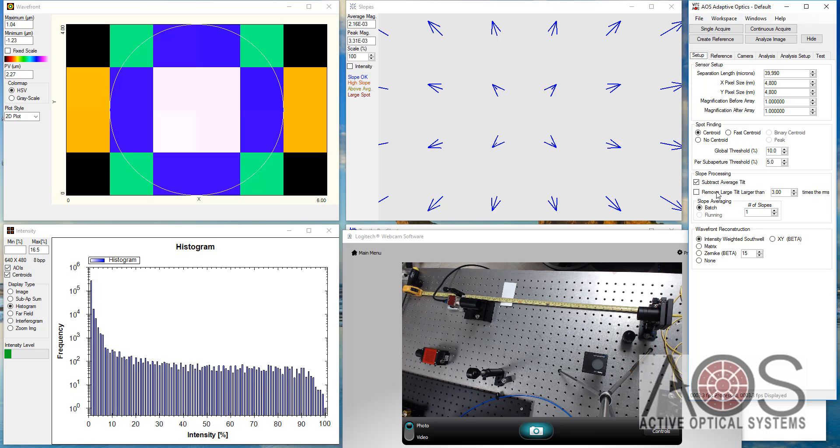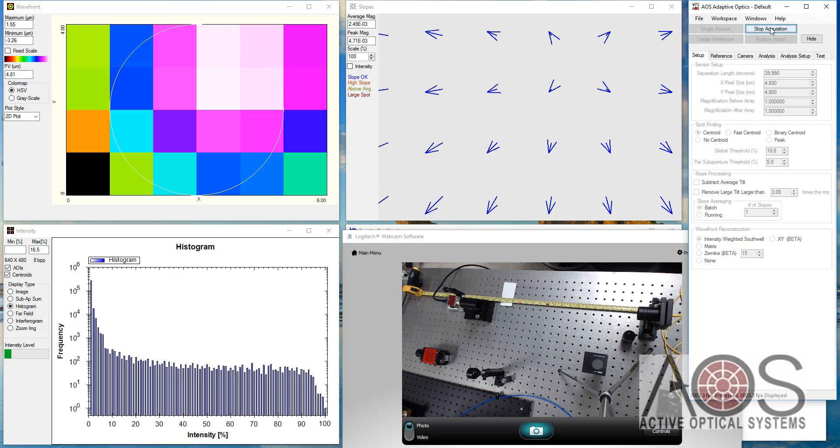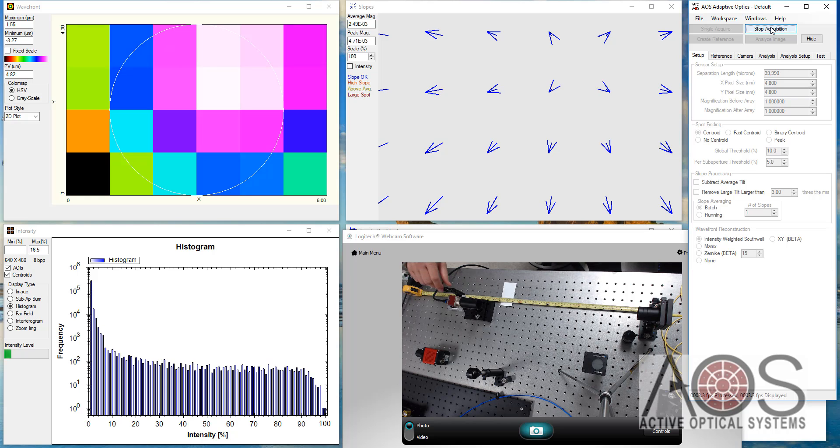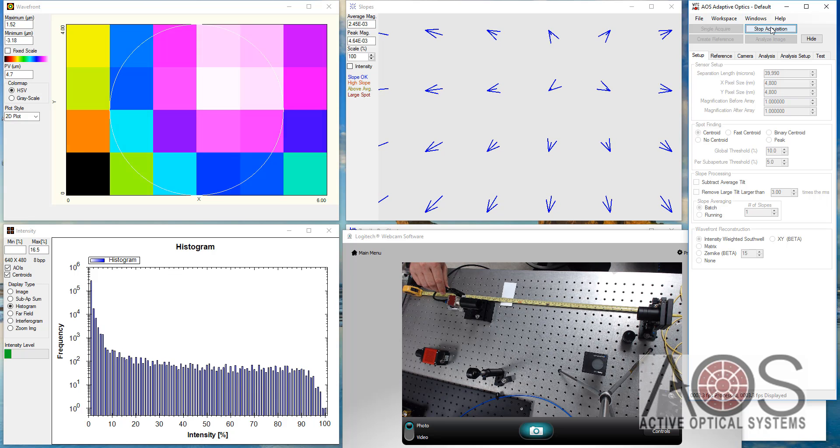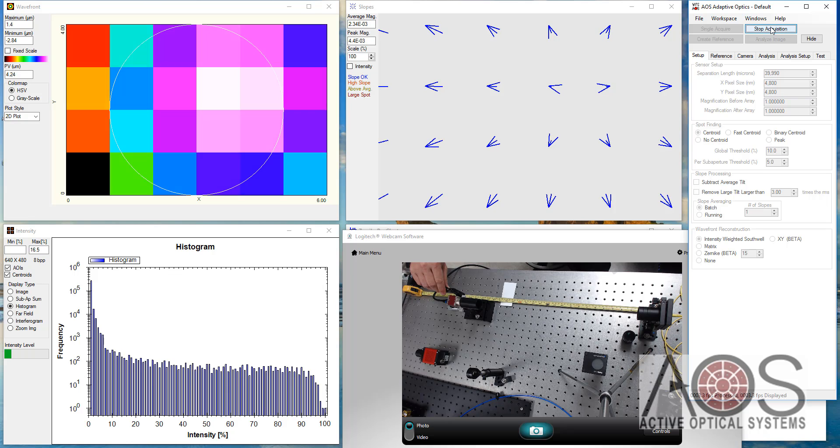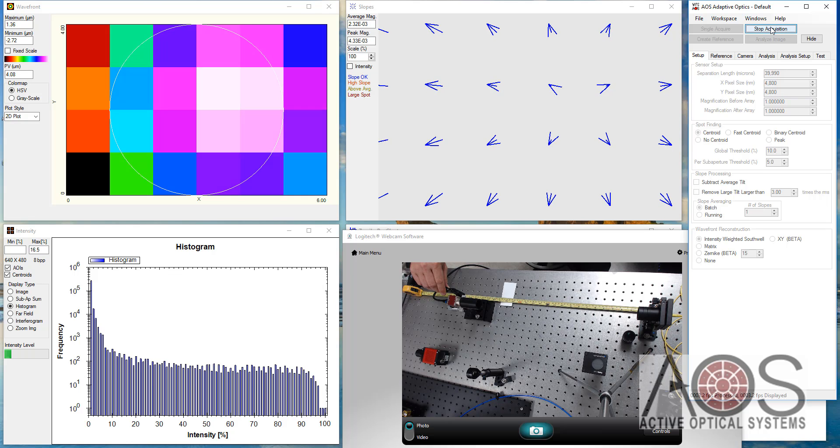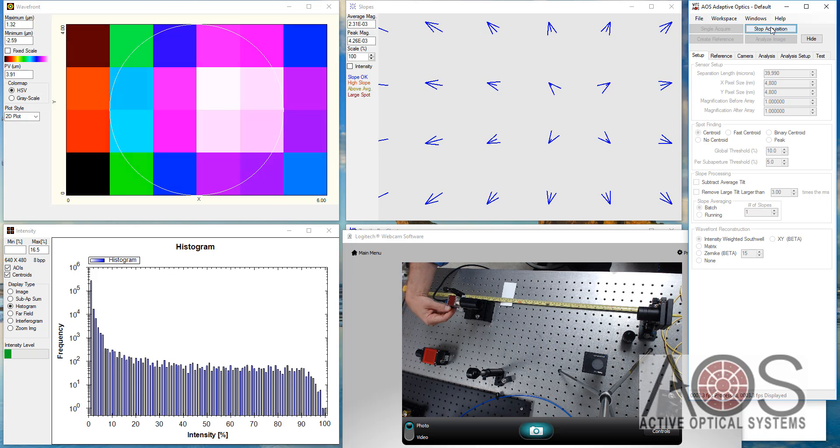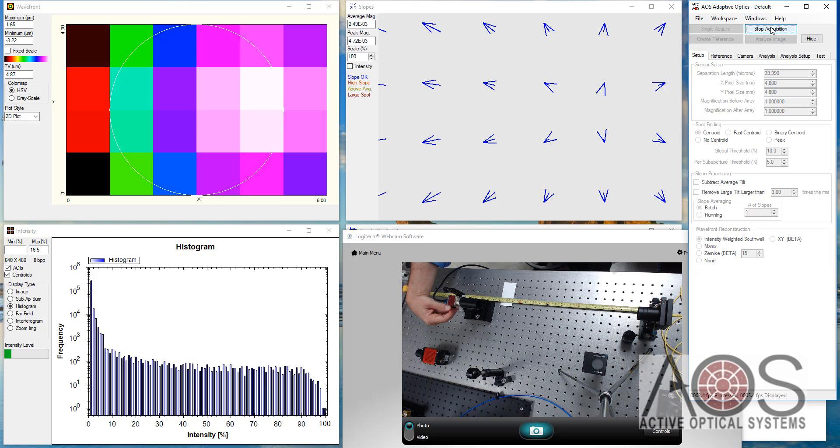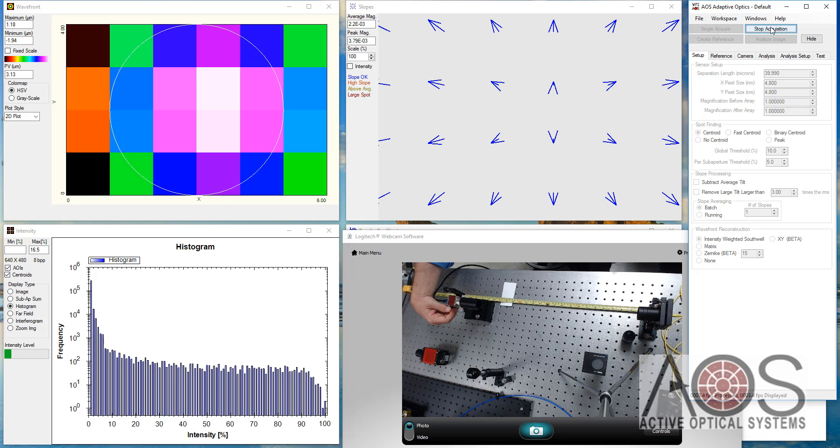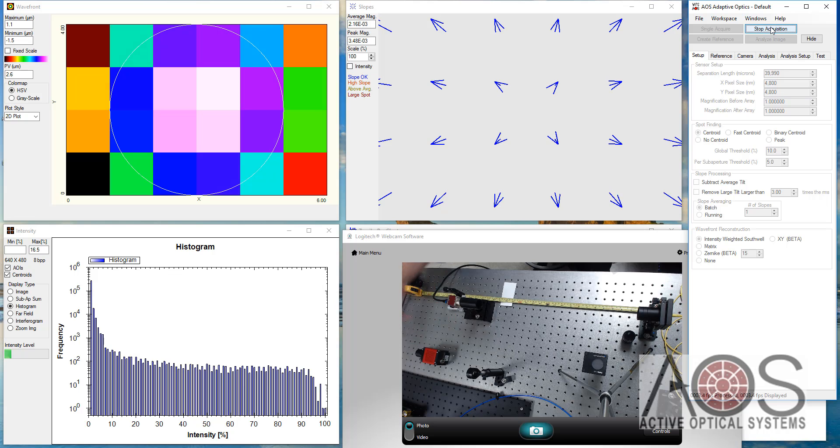Let me stop this. The other thing I want to check is I want to turn off subtract average tilt and take a look at how far tilted I am. I have a little bit of tilt on this, not too bad. I can go in and tilt the wavefront sensor in order to try to remove some of that tilt. That's good in that axis. And now I'll go to the other axis here. Oops, wrong way. And now I've got the tilt removed.